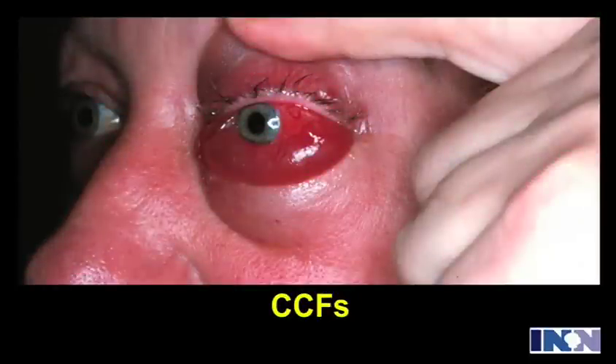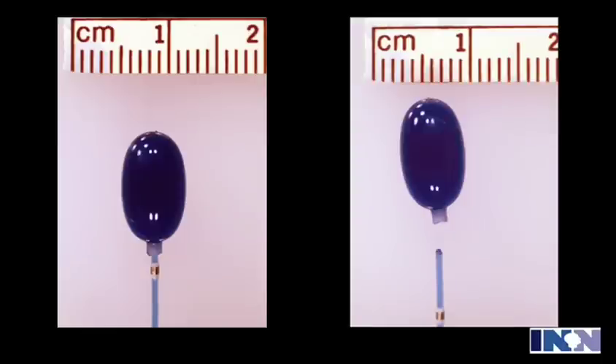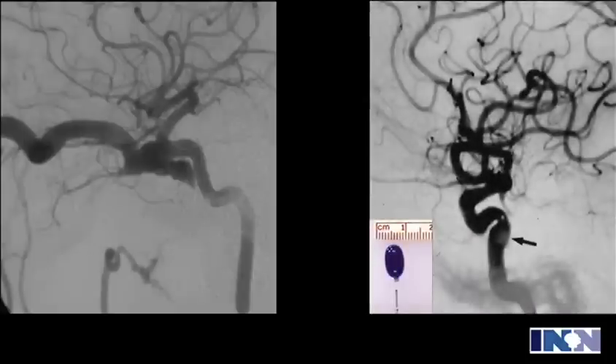Here is a patient with a hole in the carotid artery — very difficult to treat surgically. The Russian Serbinenko introduced the detachable balloon, and Dr. Hieshima from Los Angeles made a little silicone balloon. We cooperated by making a catheter with an easy detachment system. The balloon is navigated into the body, parachuted into the hole — you inflate it and the flow of blood takes it to the hole, you inflate it and seal off the hole, then detach it. Here is the same patient before and after: no surgery, no open surgery.